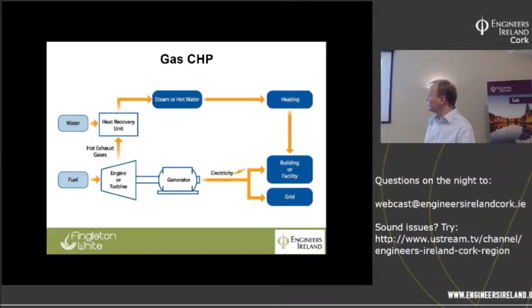There is another type of CHP, biomass CHP, which I've done some work on. Here the fuel is burnt in a biomass boiler to raise steam, and you have a steam turbine. Depending on the heat load, you select your steam turbine. The steam you need to supply your heat load is taken off typically at whatever stage of the turbine you need it for. Or, if you have a very constant heat load, you can use a back pressure steam turbine where all the steam goes through the full length of the turbine before going into the heat load. It's exactly the same thing.